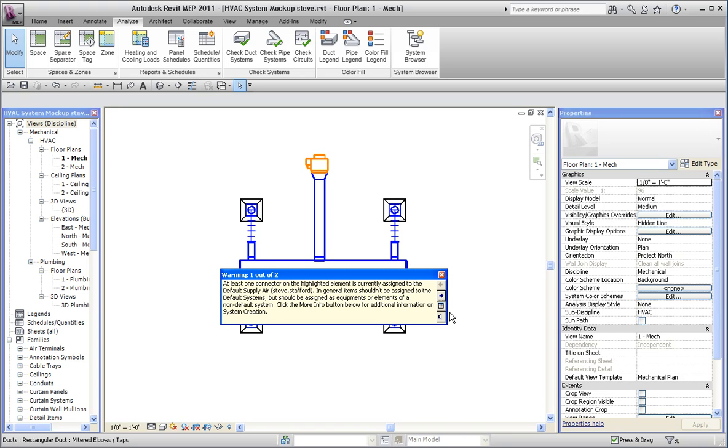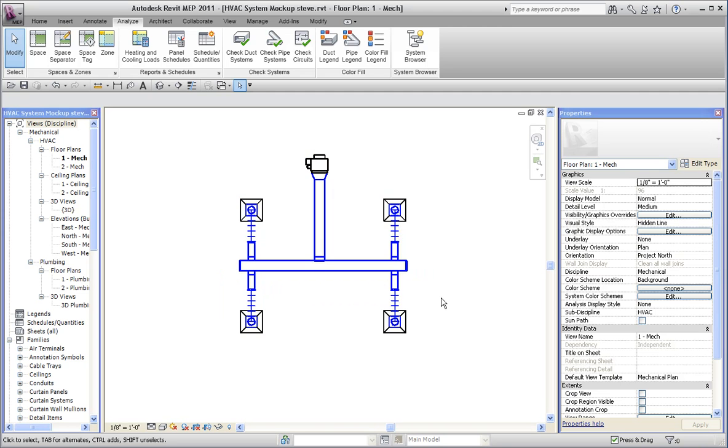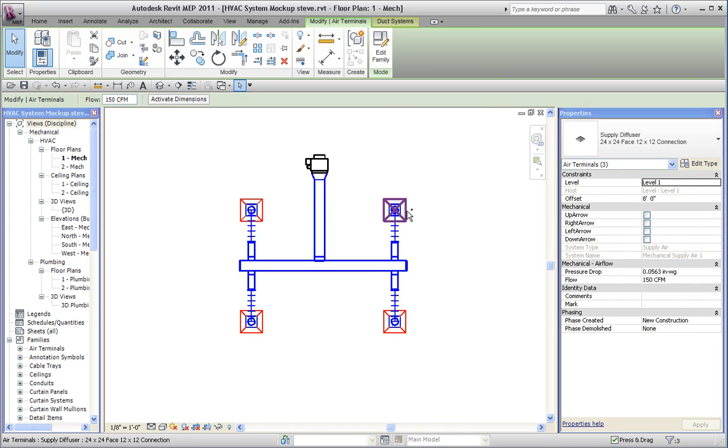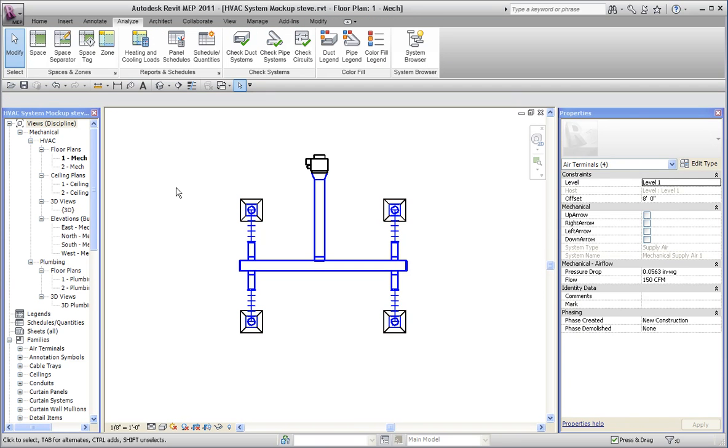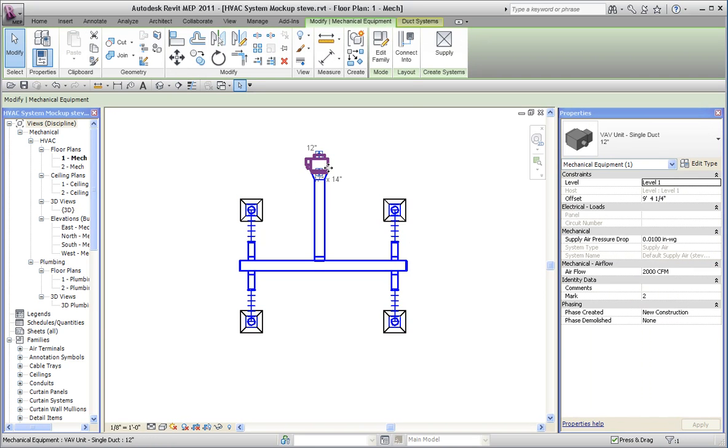But if I go to the next error message, I get one that says it's not possible to calculate the flow since all the components in the system have the flow configuration set to preset or system. At least one component is required to have the flow configuration set to calculated. That's because these connectors are set to preset. The assumption being that you're going to dial in what their values are manually and you're going to let the total accrue to the VAV box.